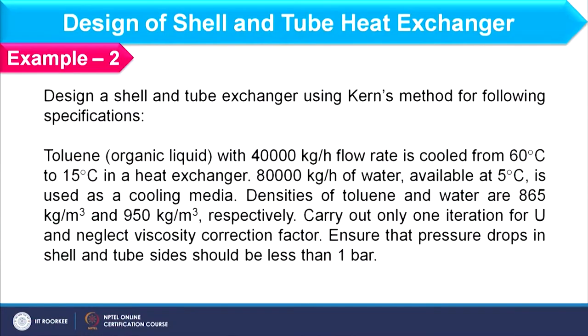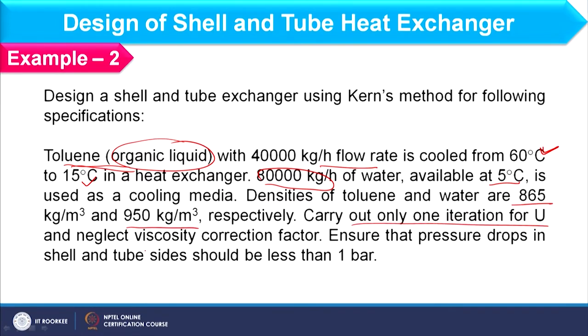If you remember the fifteenth lecture, we solved one example there, and here we will solve another example for design of a shell and tube heat exchanger based on Kern's method. This is Example 2, where toluene — considered as an organic liquid — is available at 40,000 kg/hr flow rate, cooled from 60 to 15°C in a heat exchanger where 80,000 kg/hr of water at 5°C is used as the cooling media. Density of toluene and water are given. Carry out only one iteration and neglect viscosity correction factor. Ensure that pressure drops in both shell and tube side should be less than 1 bar.